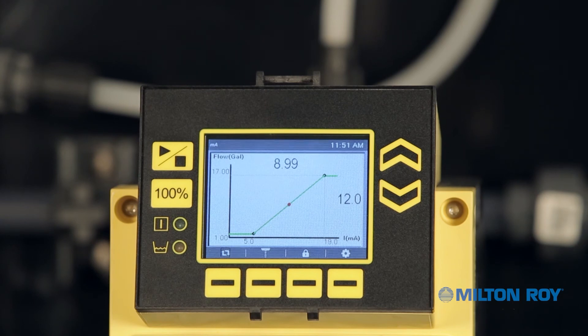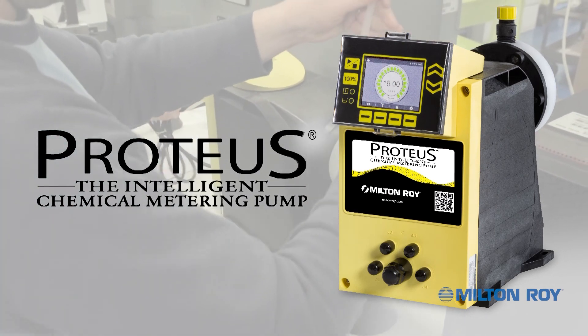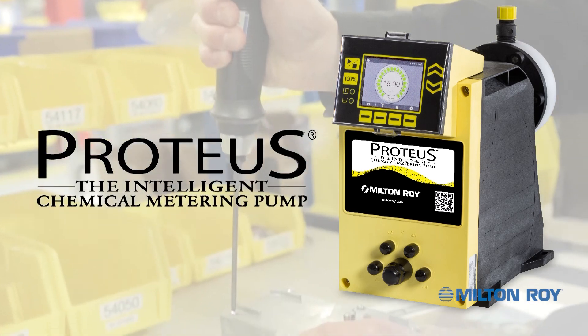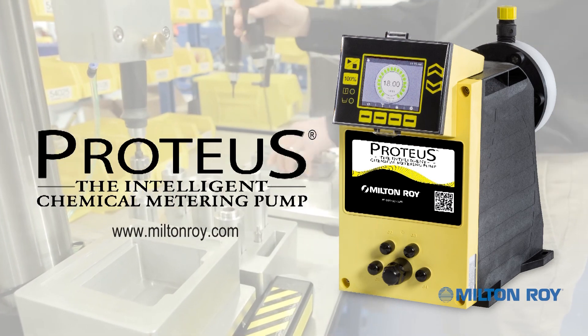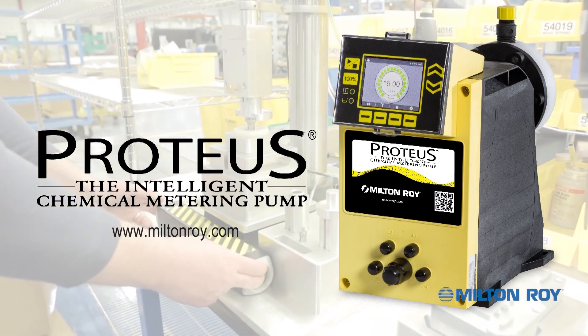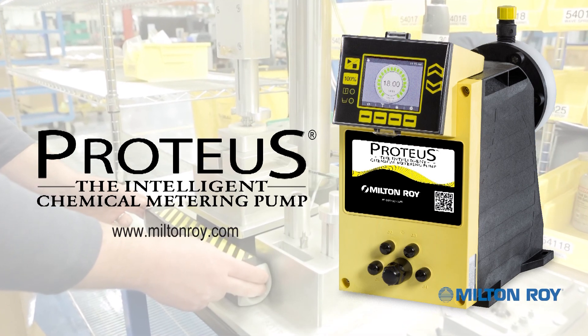We are still reading 12 milliamps but the pump is now operating at 9 gallons per hour. The pump is now configured to our specifications and we can press the Start-Stop button at the left of the screen to start the pump. For more information on this metering pump, refer to the manual or contact your local authorized representative. Milton Roy pumps are engineered to exceed expectations and are backed by a global network of highly trained field engineers and after-sales support that is second to none. Visit us online to find your local authorized Milton Roy representative. Milton Roy metering pumps offer field-proven reliability along with new innovative solutions to meet today's toughest industry challenges.